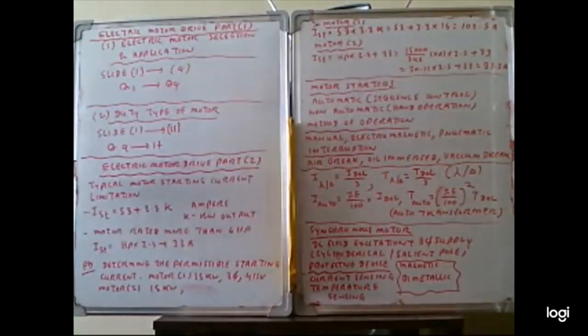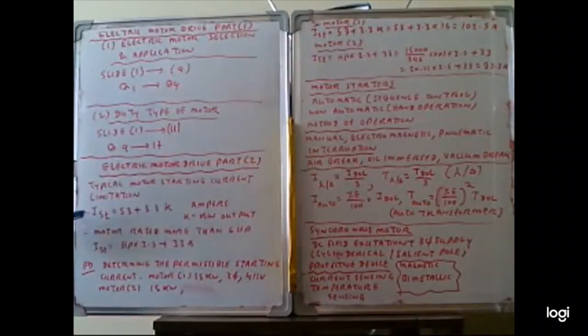Those formulas are not universal formulas; they are typical formulas supplied by the relevant motor manufacturer, relevant steel councils or the relevant supply authority. Depending on which kind of motor you are utilizing, you have to follow the appropriate starting current formula recommended by the motor manufacturer. Okay, based on those formulas, we calculate this problem: determine the starting current.